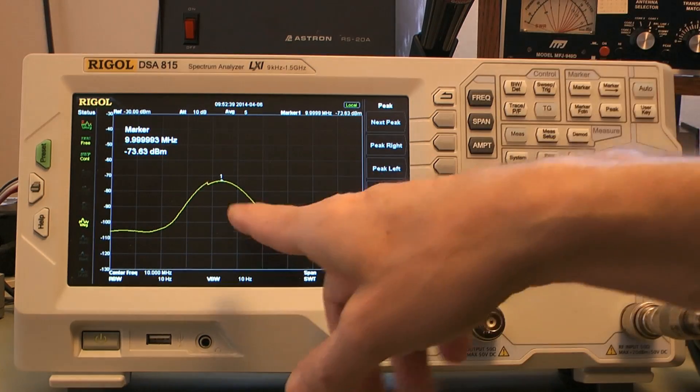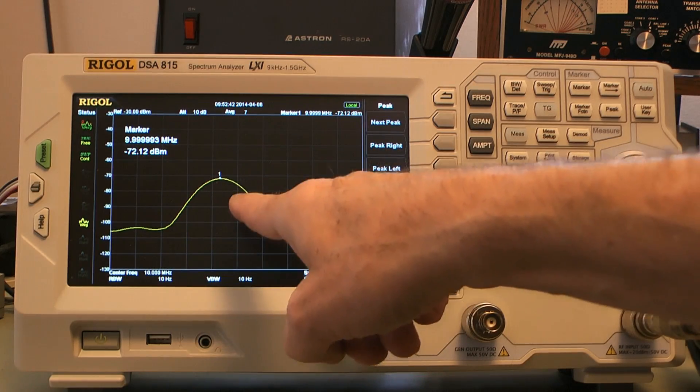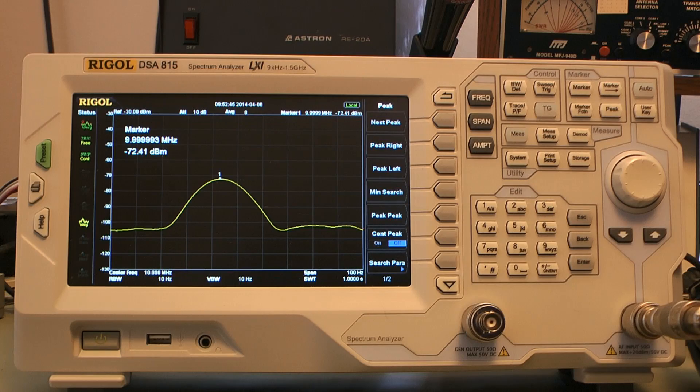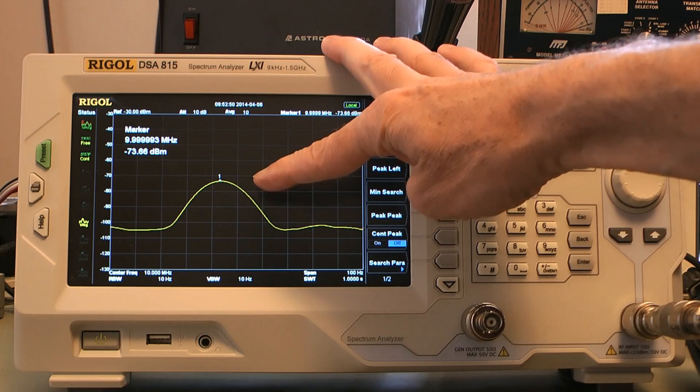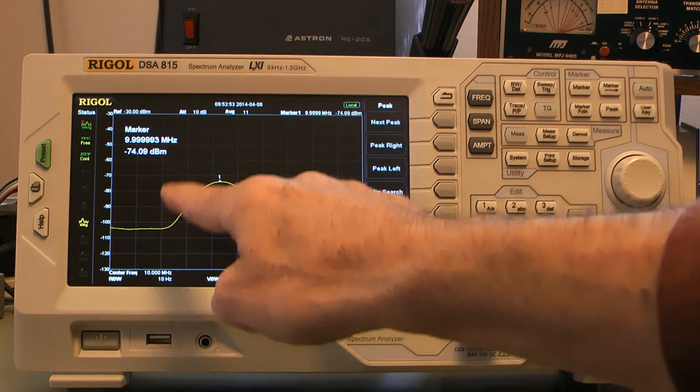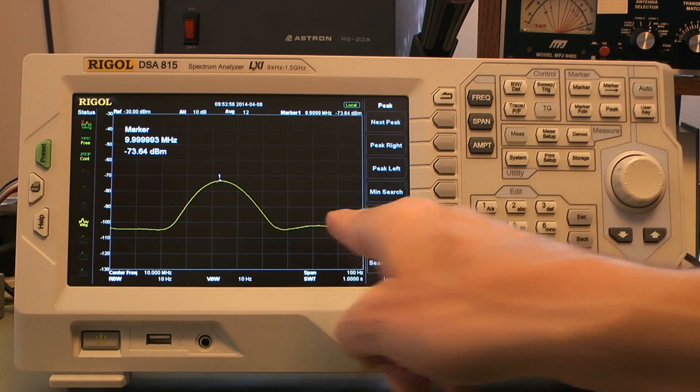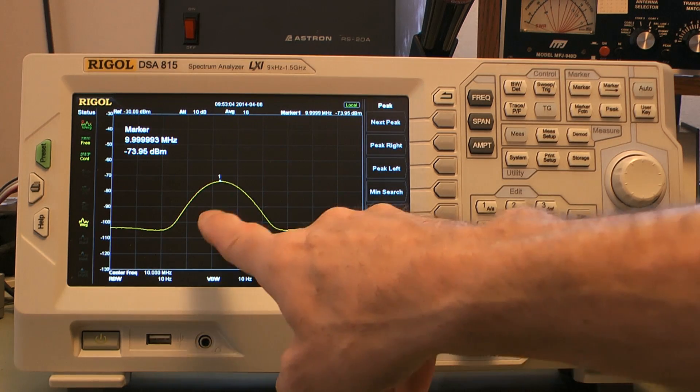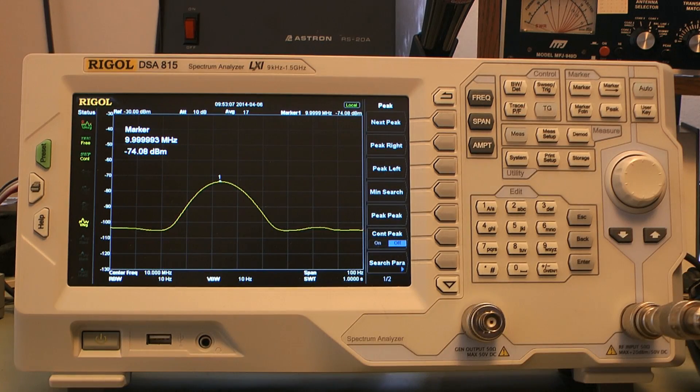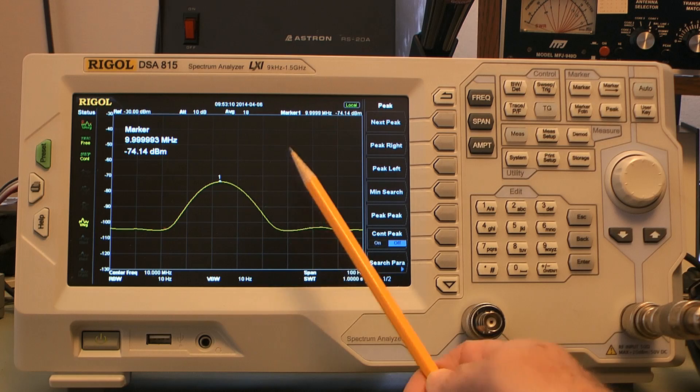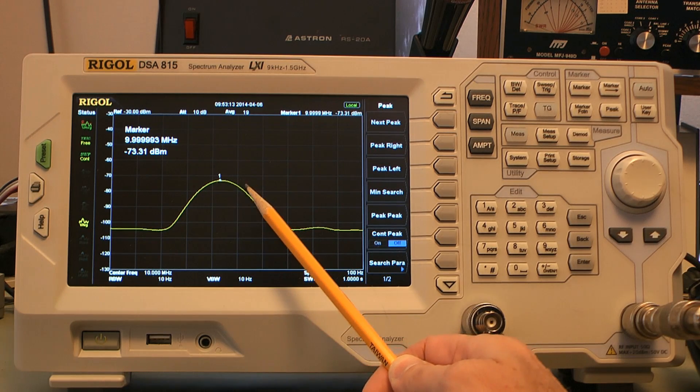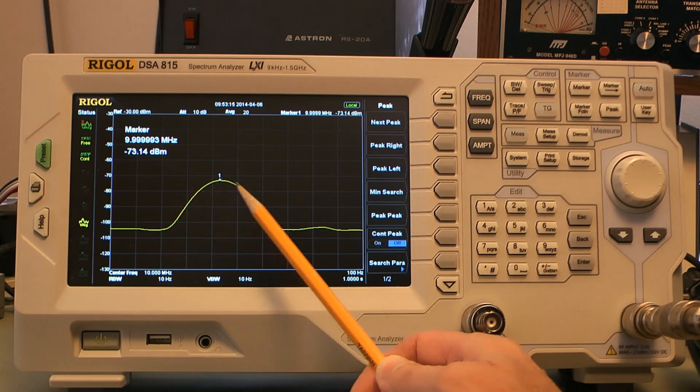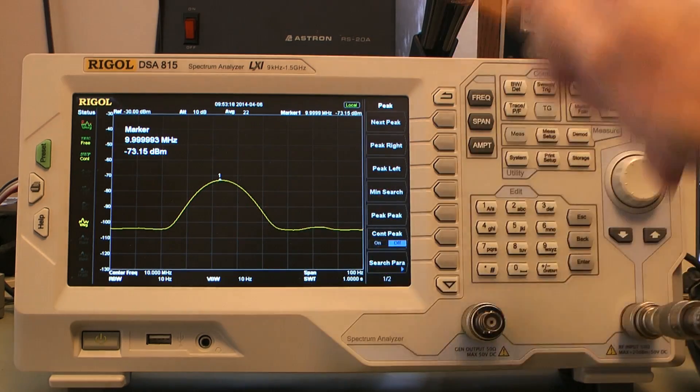It's going to start averaging these readings so that I don't have the signal jumping all over the place. It will do two things for me. One, the amplitude will settle down relatively. And two, the sides of the skirt of the signal will also settle down. Any given snapshot that you get during the one second span can give you a really lopsided signal. I want a very symmetrical signal because I'm going to use a trick to tell how far out of calibration I am by moving the reference up and down.